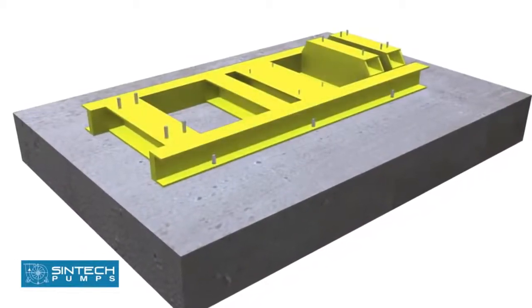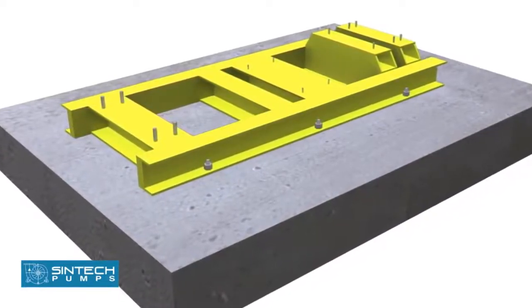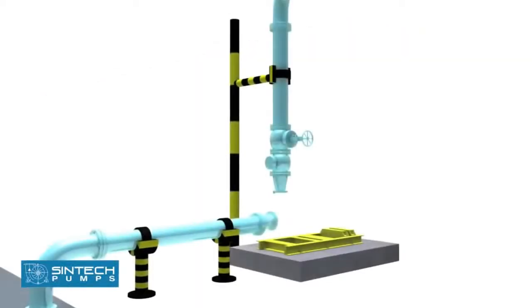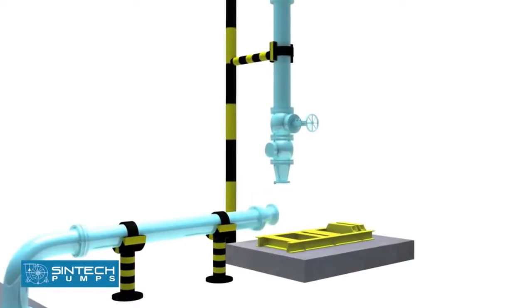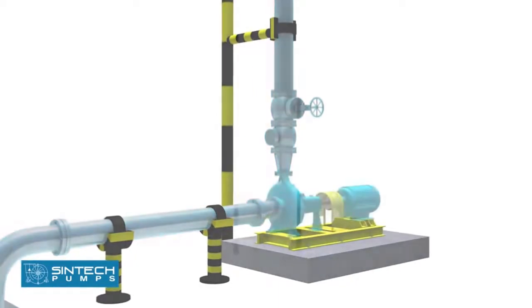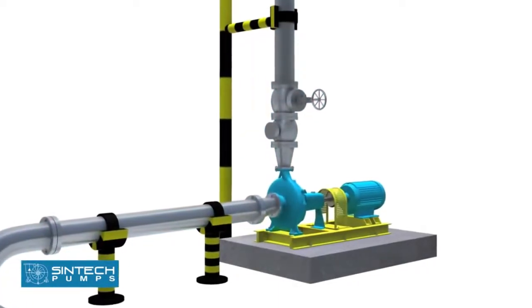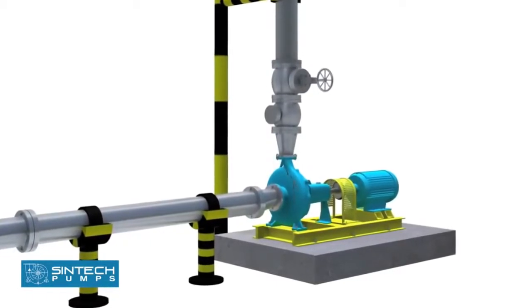The foundation bolt of proper size should be embedded in the concrete and base plate tightened, ensuring that it is level in all directions. Piping associated with the pump must be anchored and supported independently of the pump and should never put any strain on the pump casing. When the pipes are not supported, their weight is borne by the pump casing and may cause them to crack or deflect.